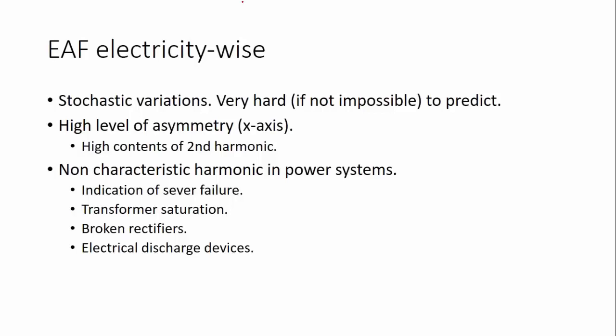When you start to drill, to bore into the scrap, the arc is very random because the scrap is in a random position. So harmonic content is high and it's very asymmetrical. When the steel is molten and you have a pool, the arc is a little more stable, and you can estimate a little better how the arc will behave. But in the beginning, it's very hard on the system because it varies a lot. The power drawn varies a lot along with the current, and the harmonics are very unstable. Besides, an electric arc furnace is pretty much like a welding machine, but huge.